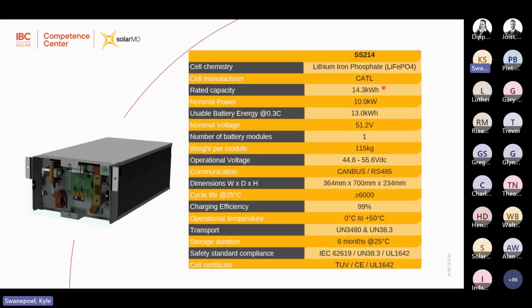And then just on the 14.3s again, there is the rack mount, which is exactly the same cell composition as the 14.3 wall mount. It's just a rack mount battery, so there is a dedicated rack that can also be purchased separately, which comes with integrated busbars. So paralleling the batteries together in the rack, and then you just take your cabling from that busbar through to your inverter or to your external DC combiner. Same specifications as that 14.3 wall mount. It's also 14.3 kilowatt hours, and it's a 10 kilowatt battery, which has 200 amp fuses, also in 51.2 volts nominal voltage, weight 115 kilos, and yeah, you can see the dimensions. So form factor wise, it is pretty compact for the amount of energy that you're getting out, and the same warranty. It's also a 12-year, 6,000 cycle energy throughput warranty.